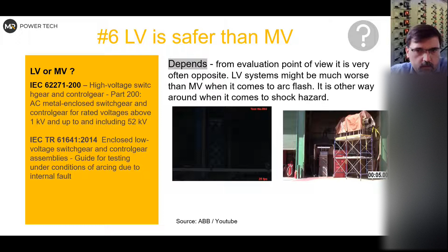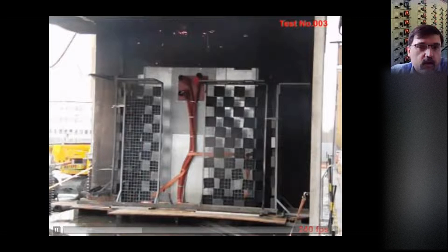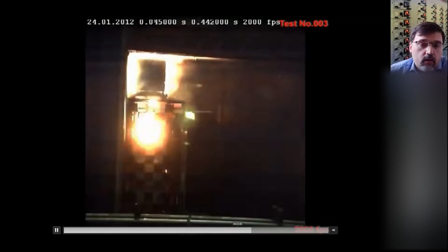So this is the test from medium voltage. It is a test for internal arc classification, but at least it gives you some idea. And I want to come back to this later as well. So you might see this. I think it's quite straightforward when you can see how things behave. And very often on medium voltage installations we have lower short circuit currents, and eventually the energy will be lower. But this is, as I said, more from the way we design.